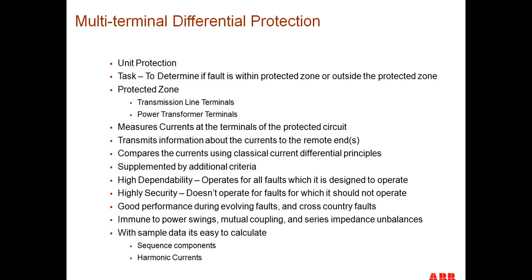In this case, the protected zone for differential relays could be the transmission line terminals, it could be power transformer terminals, or bus terminals. The same principle applies to all three. So we measure the currents at all the terminals of the protected circuit, and then we transmit information about these currents to the remote ends of the line. Each of the remote ends of the line then compares all the currents together using classical current differential principles, and then supplements this with some logic for CT saturation or open circuit CTs, and then decides whether or not the fault is internal to the area of protection or external to the area of protection.